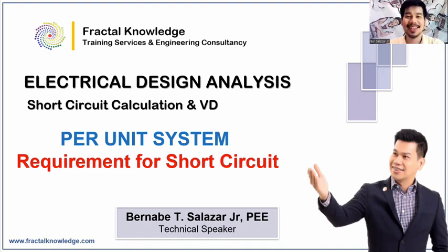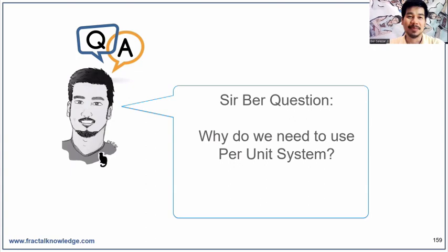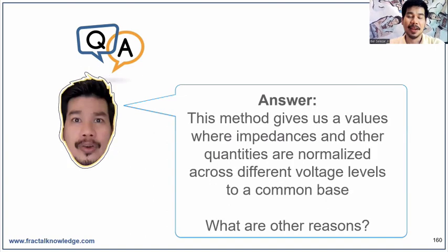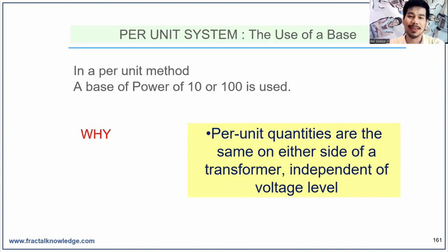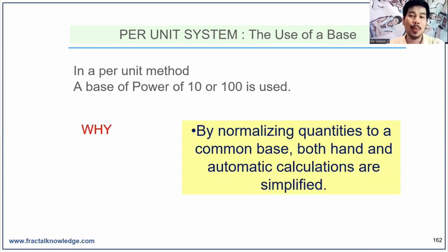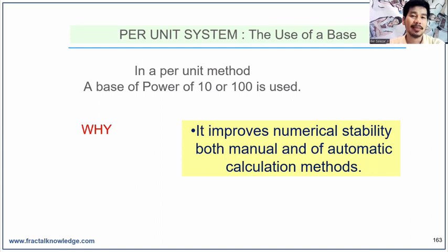This covers the last two items of base knowledge for short circuit calculation: the per unit system and the requirements of short circuit. You may ask why we need to use the per unit system. Per unit methods give us values where impedances and other quantities are normalized across different voltage levels to a common base. Quantities are the same on either side of a transformer, independent of voltage level, simplifying both manual and automatic calculation and improving numerical stability.